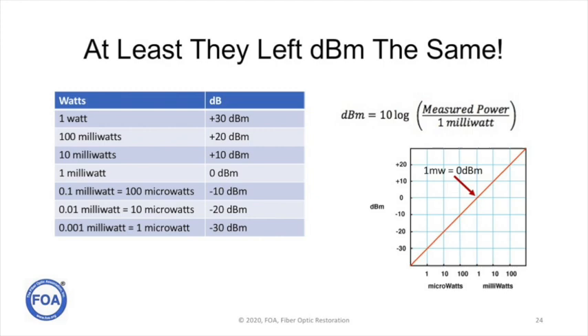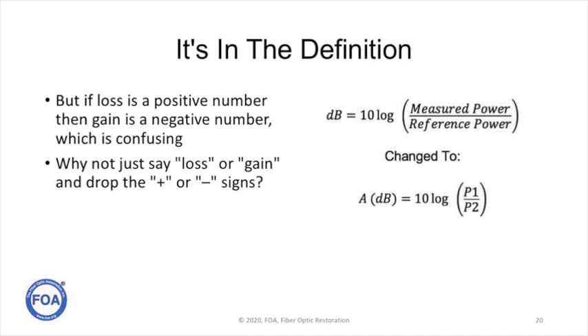So that's why an optical loss test set, or OTDR, defines loss as a positive number and gain as a negative number. And if you do the same measurement with meter and source, you'll find that loss is negative, gain is positive. It's all in the definition.